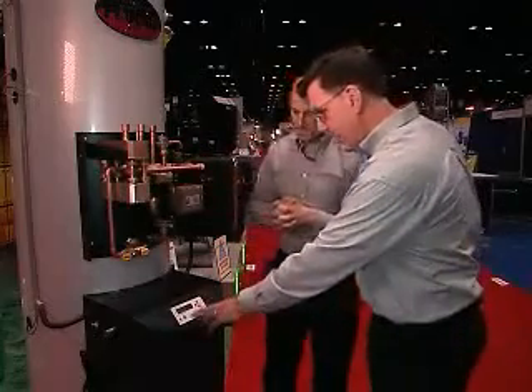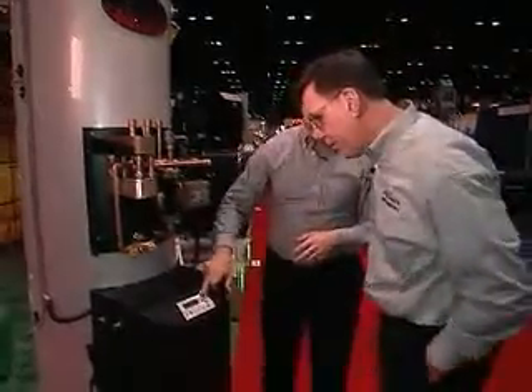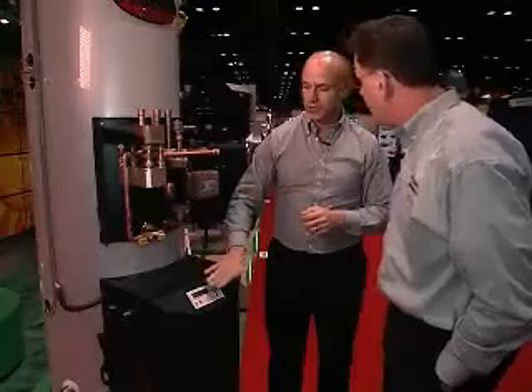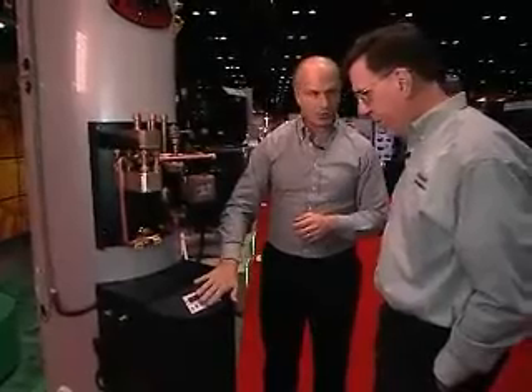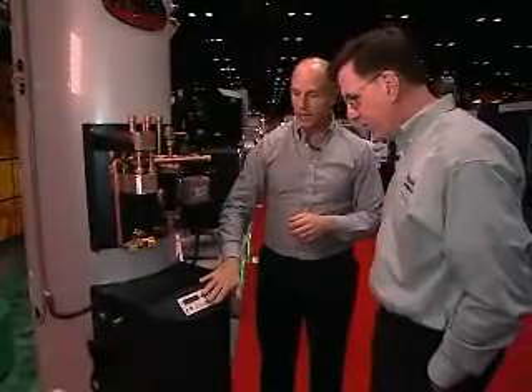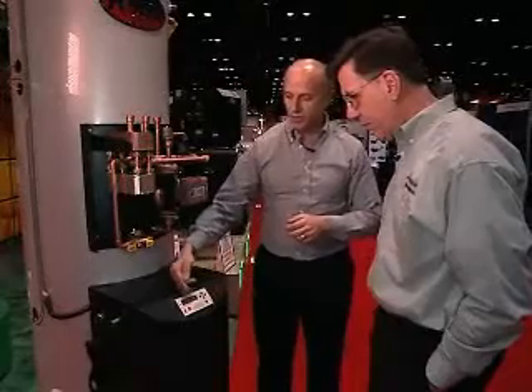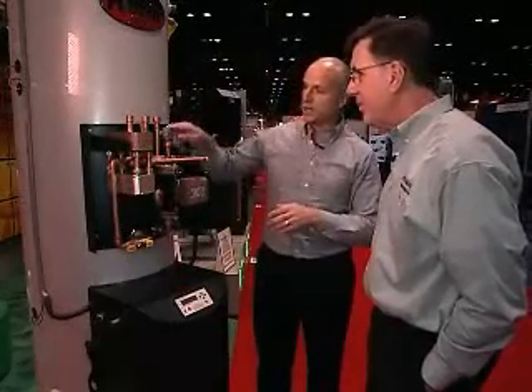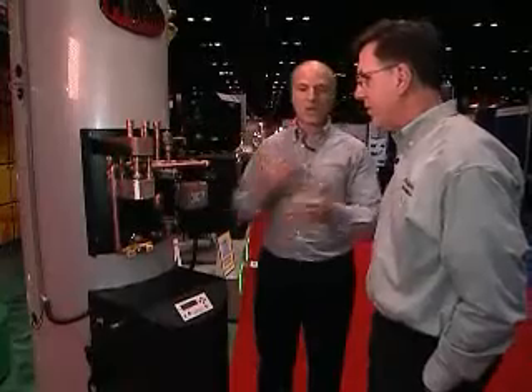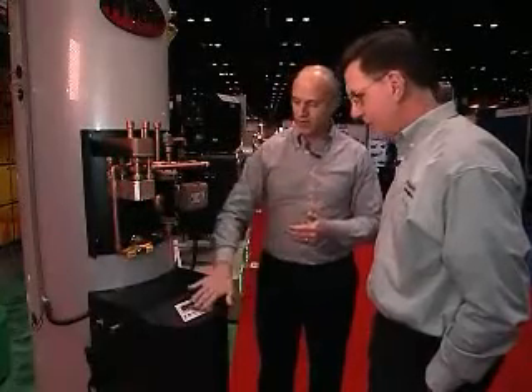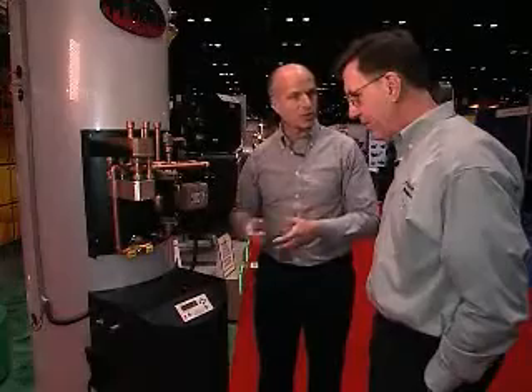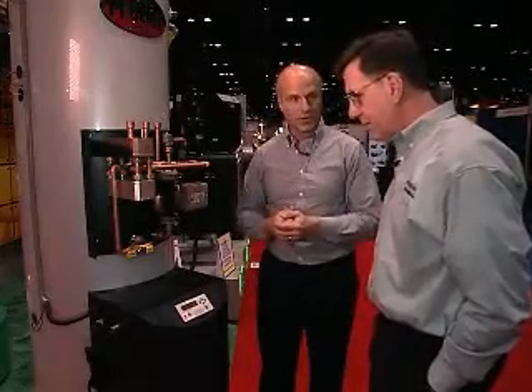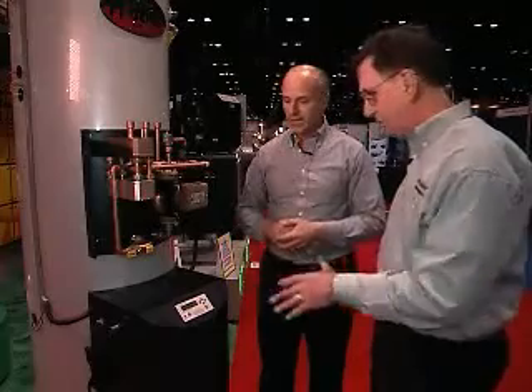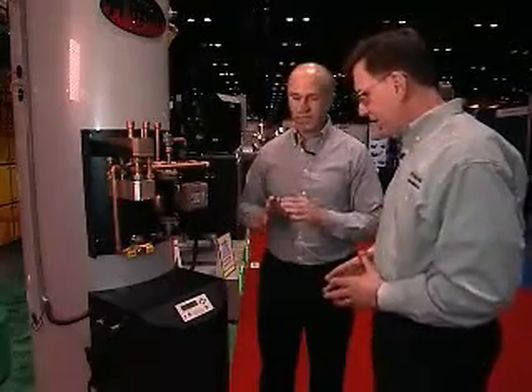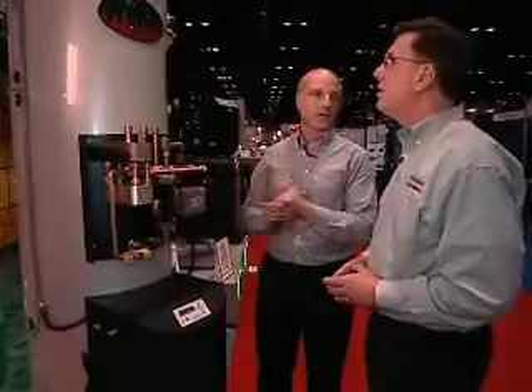Nice. Tell me about the controls. Everything's programmed right through the display. This is a multi-line display, and we can set the reset curve right through here, water temperatures right through the display itself, and it has all the troubleshooting. It operates your pumps. It'll give you output temperatures and a lot of different information on the system, and it makes it very user-friendly because everything is in words. It's a two-line, backlit 20-character LCD display. So not a lot of codes you have to go look up? Not a lot of codes, it's all there. Real simple to operate, and it gives the contractors a lot of information to see exactly what the system's doing.